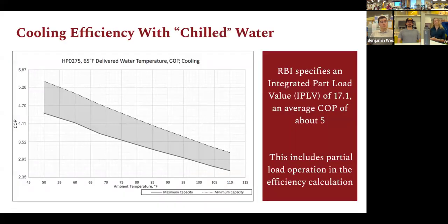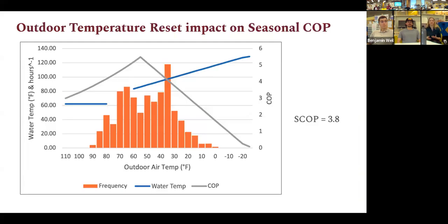Similar to heating, this graph shows the cooling efficiency of the heat pump in cooling mode. And as the temperature increases, the coefficient decreases. It's harder to cool the air than heat it. This graph here shows the frequency of the temperatures we experience in relation to the coefficient of performance and the hot water temperature. So as the temperatures decrease, the hot water temperature rises. And as temperature also decreases, the coefficient of performance decreases.